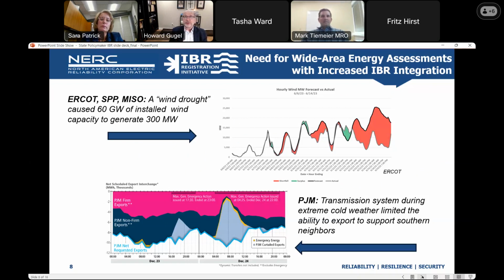In June of last year, 2023, there were situations across a wide swath, from Texas all the way up into MISO and SPP, where there was 60 gigawatts - 60,000 megawatts - of installed wind capacity. At particular times of day we only had 300 megawatts of generation because there was simply no wind available, no fuel for those generators. So while it looks like you have lots of capacity, 60,000 megawatts of generation, you could really only get an output of about 300 megawatts during that time.